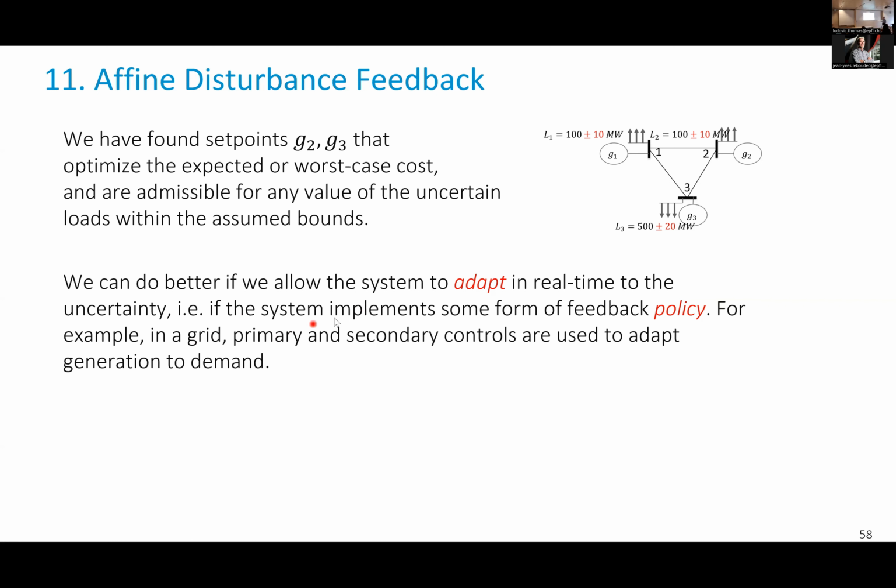That's primary control. And if the frequency-based control, primary control, is not sufficient, there's a secondary control done by the so-called system operators like Swiss Grid, that monitors the power balance. And if they see that there is some imbalance in one direction or another, they send explicit signals at the time scale of approximately a second to all generators that participate in what is called regulation services. Your PV panel doesn't do that.